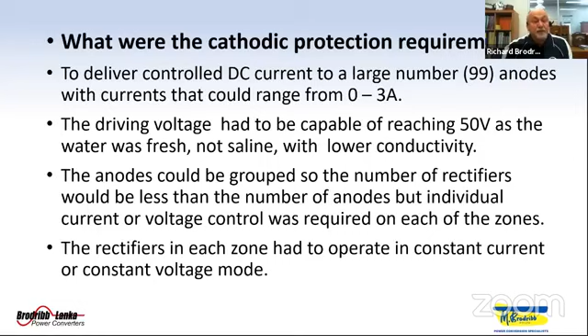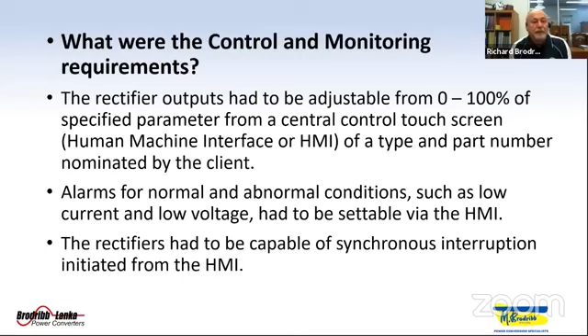The control and monitoring requirements were complex. The rectifier outputs had to be adjustable from 0 to 100% of the specified parameter, say voltage or current, from a central control touchscreen, a human machine interface, or HMI, of a type and part number that the client had nominated. That meant the software and interface was something we had to adapt ourselves to for their particular equipment.